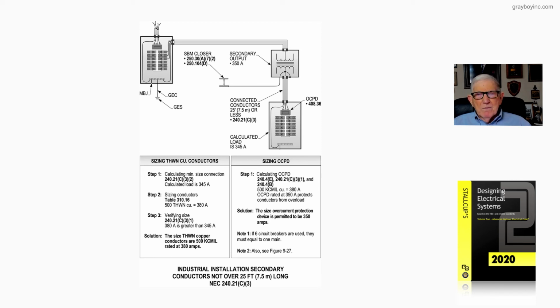But if I rounded it up to 400, then it would not protect step 1 or step 2 in sizing the conductors. Sizing the THWN copper conductors is illustrated in the boxed-in information to the left. And that's what our figure 20-37 is illustrating. And if you wanted to pick up more about these tap rules, transformer secondary conductors, start in Stallcup's Electrical Design Book, Volume 1, and start with figure 9-22, and you will go through a series of figures that will show you all the tap rules of secondary transformer conductors of 240.21(C) as in car.